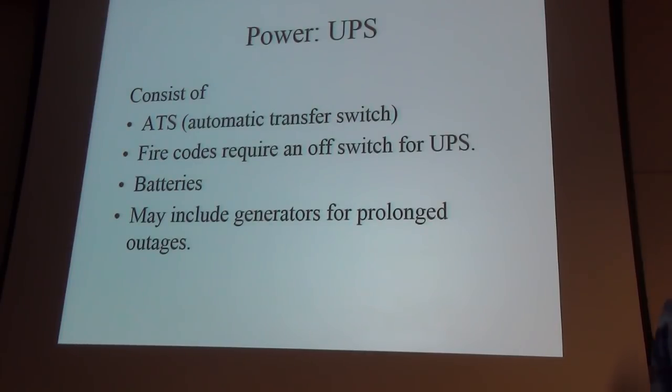True story: I believe it was August 2006, when a power trip in northeastern Canada or the northeast US caused a blackout including Michigan for three days. At General Motors, they were happy they had a generator. They turned it on, and after one hour the generator stopped. The fuel tank was empty. For the last five years, every month they conducted a test — ran the generator an hour on a clipboard — and forgot to refill the fuel tank. Generator: good. Care and feeding of generator: even better.